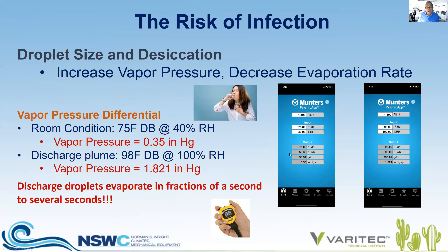Let's explore why this occurs. If you want to examine the states of air on your phone, I invite you to download for free Munters' psychrometric app — I use this every day. So why is the rate of desiccation of droplets expressed by an infected person important? Looking at the vapor pressure differential: in a room environment with a design set point of 75 degrees at 40% RH, the vapor pressure is 0.35 inches of mercury. A discharge plume from an infected person will be at least 98 degrees at 100% RH, giving a vapor pressure of 1.821 — an extreme differential.